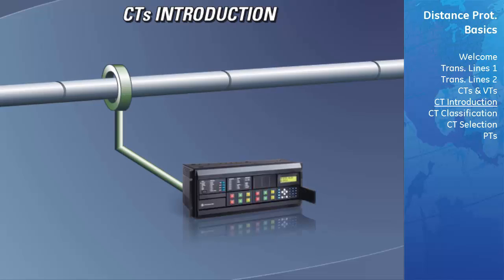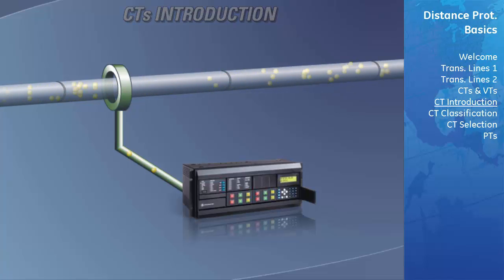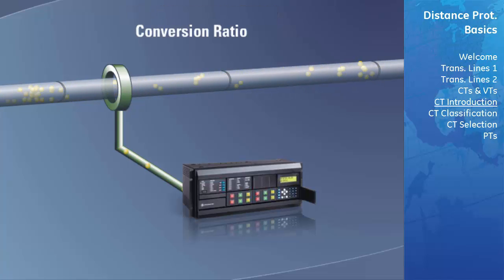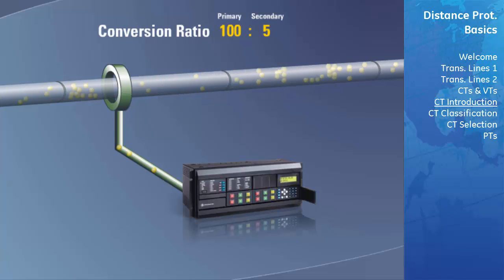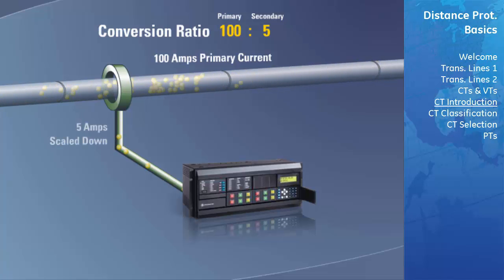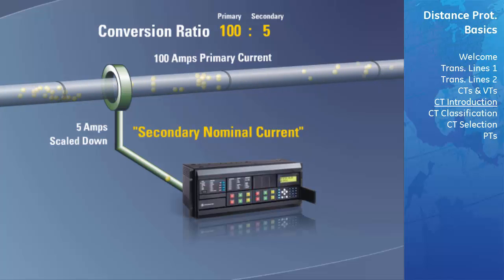The function of a current transformer, or CT, is to take a current flowing through a wire or cable and step it down to a magnitude that a protective relay can measure. A primary characteristic of CTs is their conversion ratio. In this example, our conversion ratio is 100 to 5, meaning that if 100 amps are passed through the primary phase wire, the CT will scale this down to 5 amps and direct it to the relay via the secondary windings. The 5-amp measure is known as the secondary nominal current.